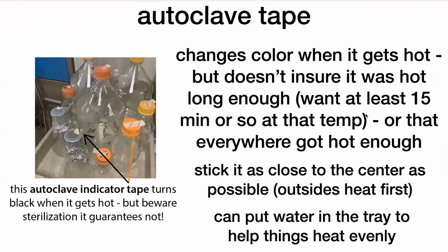Before you stick those bottles, or whatever you're sticking, into the autoclave, you want to stick on autoclave tape. This is a heat sensitive tape that is going to change color when it gets hot. This is really, really helpful so that you can see if things have been autoclaved. But it's not perfect. It tells you if things got hot, but it doesn't tell you how long they got hot for. And it doesn't tell you that everything in there got hot for the same amount of time and with the same thoroughness. It's kind of like a yes or no: did it get to this hot point?